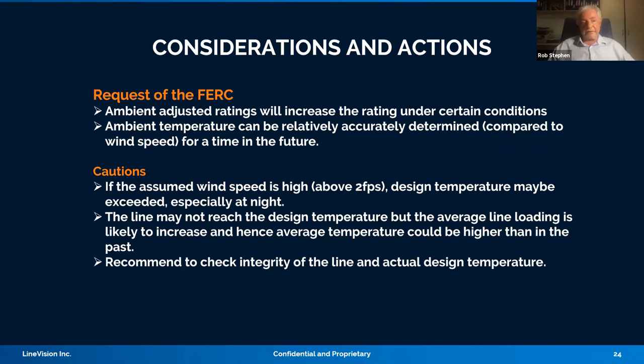So considerations and actions. The request of FERC is that ambient adjusted ratings will increase the rating under certain conditions. This is really what the aim here is: let's try and get rid of these constraints, especially if they're thermally rated. There's a lot more we can do besides static ratings, which are normally deterministically determined, and that's 100% correct. Ambient adjusted ratings, which were in fact used by PG&E in the early 90s with the Atlas system, can increase the ratings under certain conditions. And your ambient temperature can be relatively determined for a time in the future. But we just need to be a little bit cautious here, as I said.